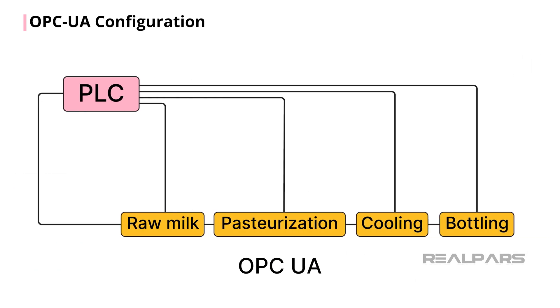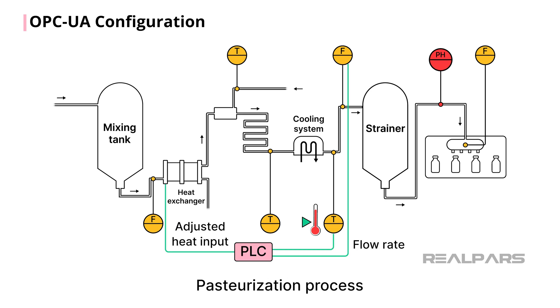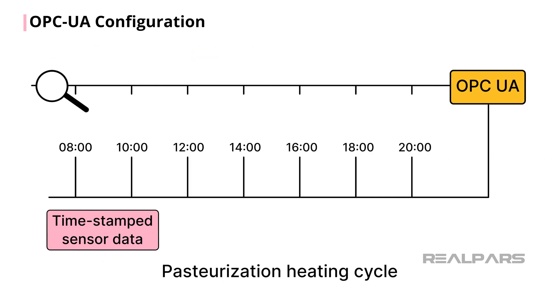OPC UA plays a key role in the adaptive feedback loops integrated into programmable logic controllers. These advanced control schemes can monitor the milk product at every stage of production, and initiate corrective actions before quality parameters are violated. For instance, if the temperature at the outlet of the HTST drifts, the system can use the milk flow rate to calculate the appropriate adjustment to the heat exchanger's heat input.